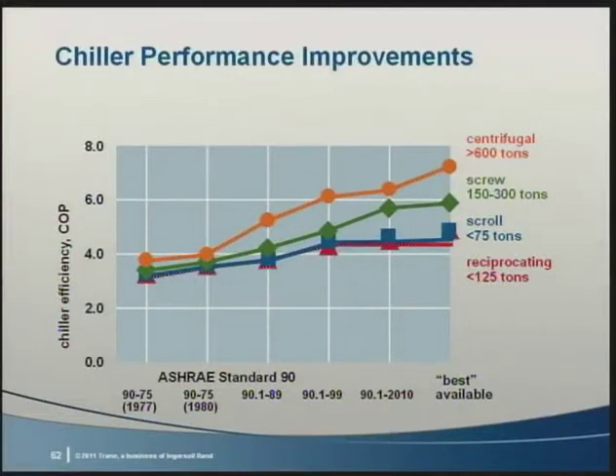Well, we often think of kW per ton for a chiller. Another measure of chiller efficiency is COP, or coefficient of performance. We can calculate it by dividing 3.516 by the kW per ton. For COP, higher is more efficient. Now this chart summarizes the dramatic improvements in chiller efficiency during the last 3 decades. It shows the minimum requirements per ASHRAE Standard 90 between 1977 and 2010, as well as the best efficiency we could find today.